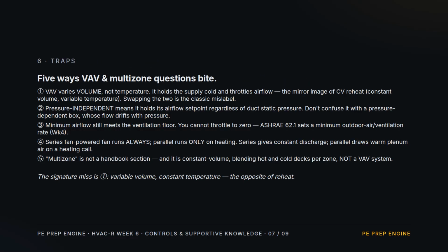Traps. Five ways this bites. One. VAV varies volume, not temperature. The mirror image of reheat. Swapping them is the classic mislabel. Two. Pressure independent means the box holds its airflow set point regardless of duct static pressure. Don't confuse it with a pressure-dependent box. Three. The minimum airflow still meets the 62.1 ventilation floor. You can't throttle to zero. Four. The series fan-powered fan runs always, the parallel only on heating. Five. Multi-zone isn't a handbook section, and it's constant volume, blending hot and cold decks per zone. Multi-zone is a different animal from VAV.